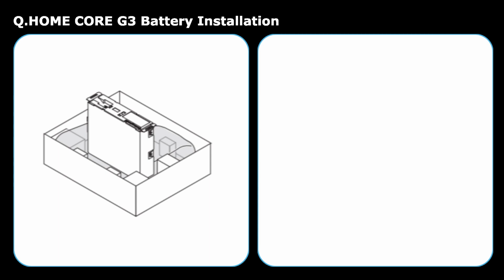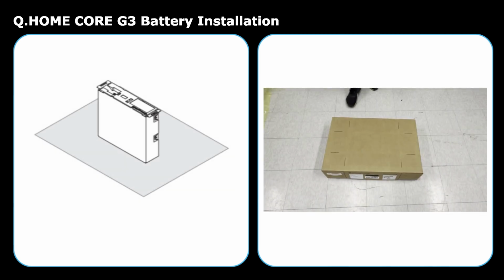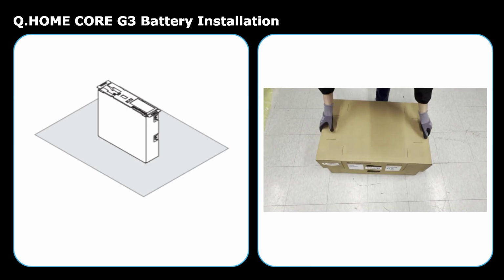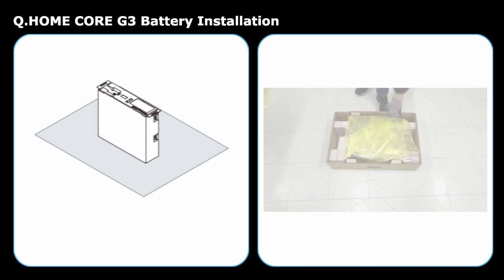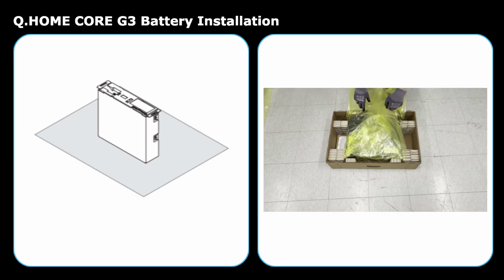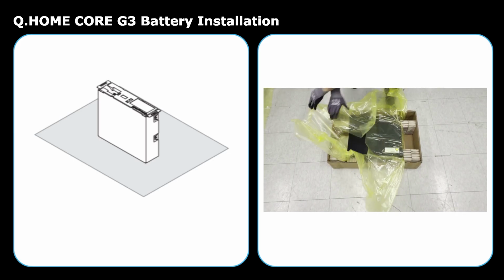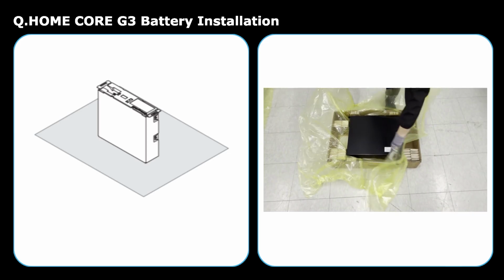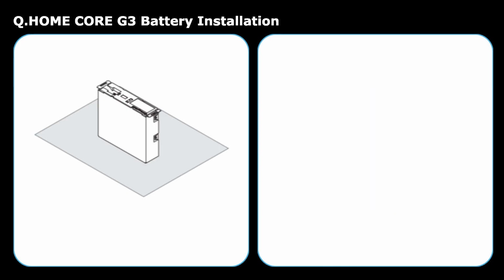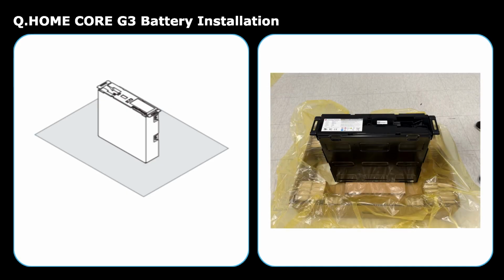The Q.HOME CORE G3 requires a total of 4 battery modules. Each module is packed individually. When removing a battery from its box, be extremely careful not to bend or break the bracket on the front. To prevent damage, always store the battery modules either upright or laid flat on a level surface.